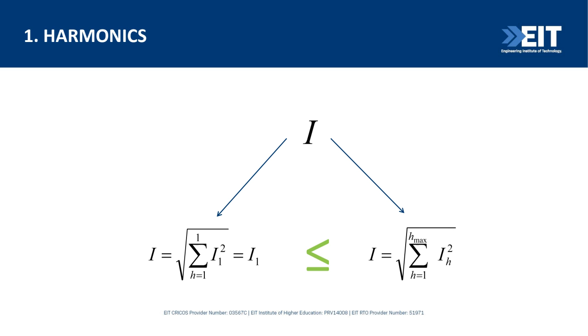Because we do have harmonic components in currents, we will have added losses in transformers. When we have lamps and different kinds of equipment in our houses, with digitalization, we have a lot of digitalized things: laptops, iPads, tablets, different types of mobiles and lamps. These generate harmonics, which means we are drawing more current from transformers, increasing losses, which will affect their thermal capacity and maximum loading.